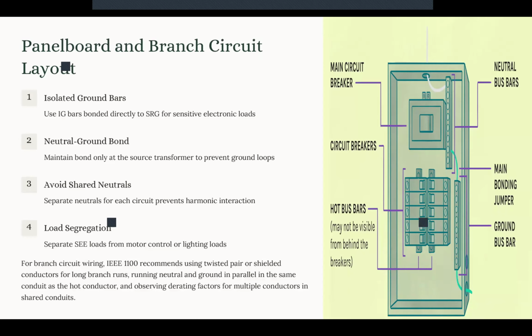Now, each power distribution system also has some panel boards that basically distribute the power between the equipment. They also have some requirements that are recommended by IEEE 1100. We do that to make sure we have clean, stable, and noise-free power delivery when we talk about sensitive electronic equipment. Now, what are those recommendations? One is we have to have isolated ground bars. What that means is we have a dedicated ground bar connected directly to the signal reference grid, that SRG we talked about, and it is independent of other equipment grounding conductors. That way we stabilize the ground reference and provide that low impedance, less than 1 ohm connection.